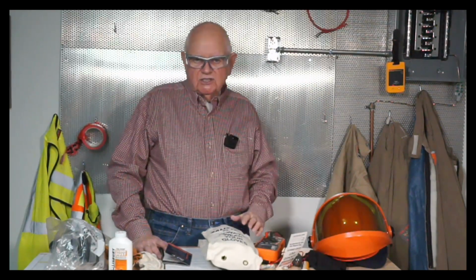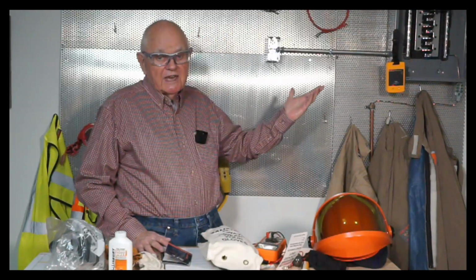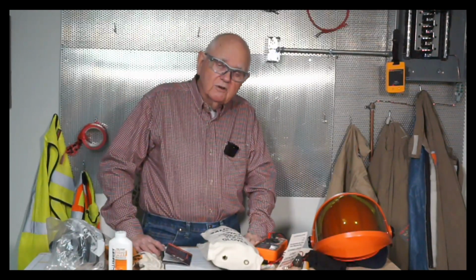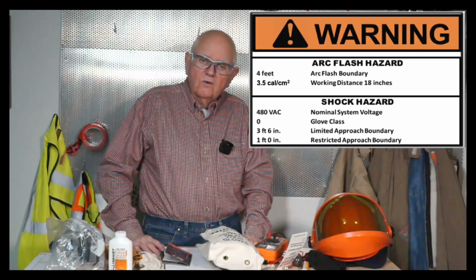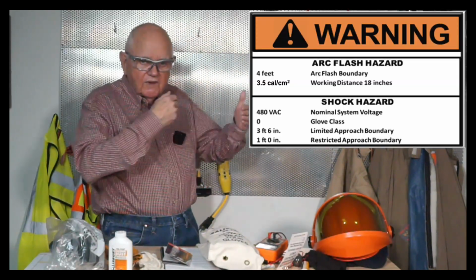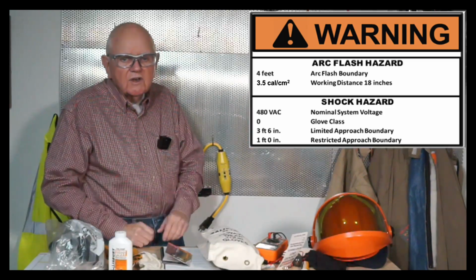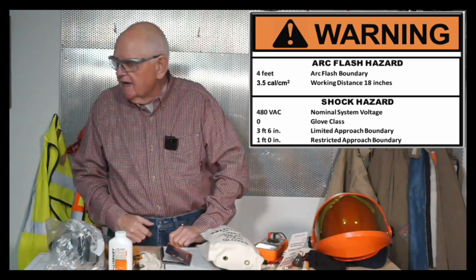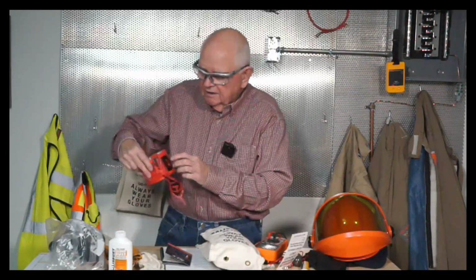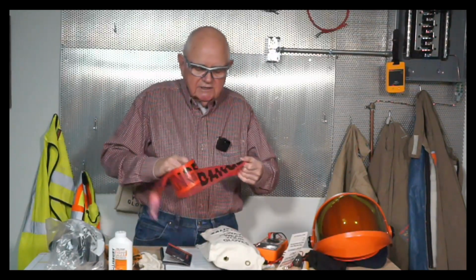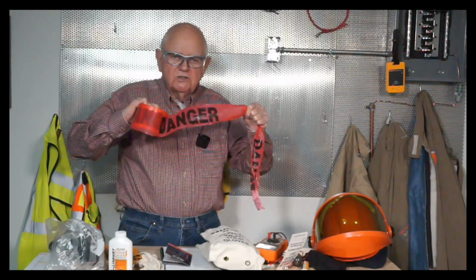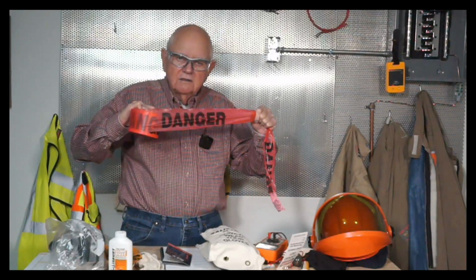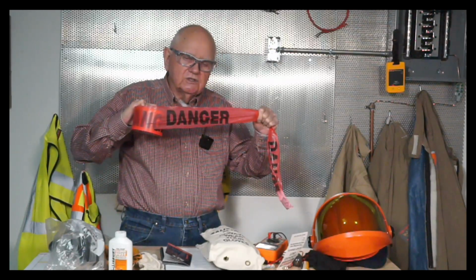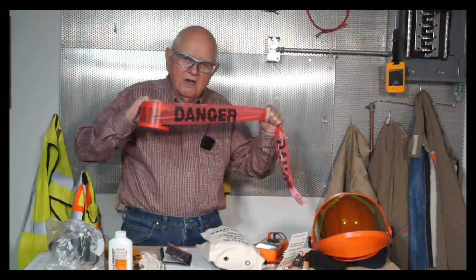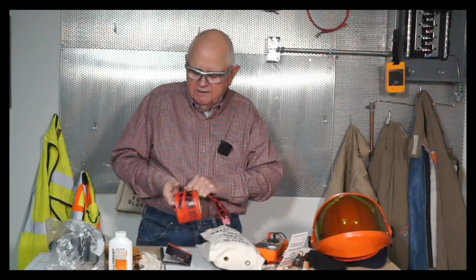That's for shock protection. The arc flash boundary is based on burn protection. And in this case, the arc flash boundary is actually a little bit further out than the limited approach boundary. The arc flash boundary is 4 feet or 48 inches. So what's further out? Well, 4 feet is further away than 42 inches. So I have to set a physical barricade at the furthest of those two boundaries. Whatever type of barricade you're using, set up a physical barricade to make sure that nobody gets burned or shocked. And how do you know that? Look at your boundaries and see which one is furthest away from the live parts. That's where you set your physical barricade then.